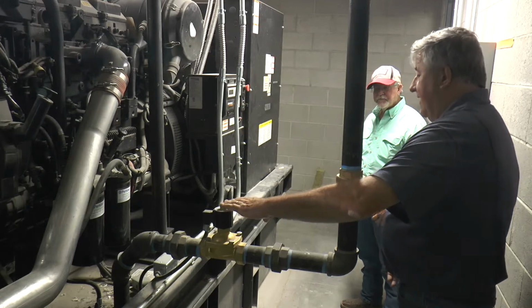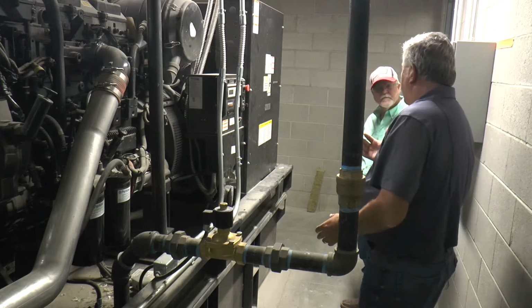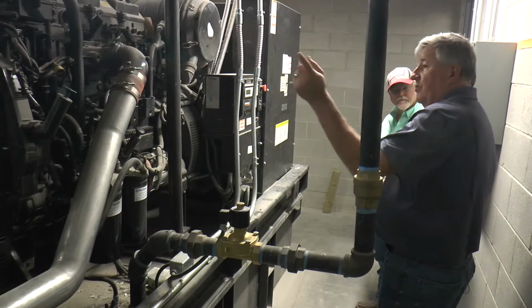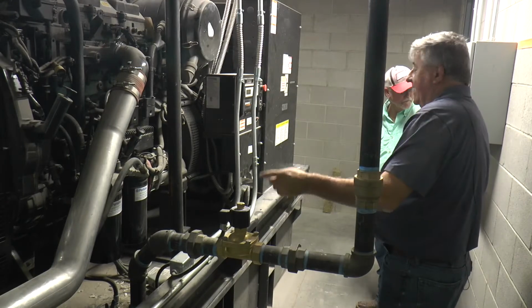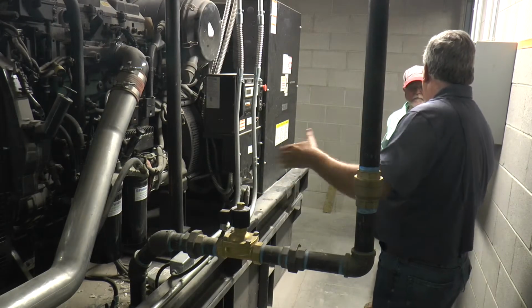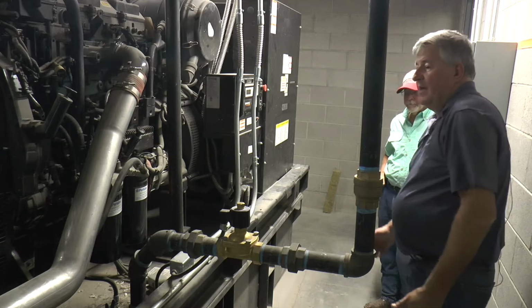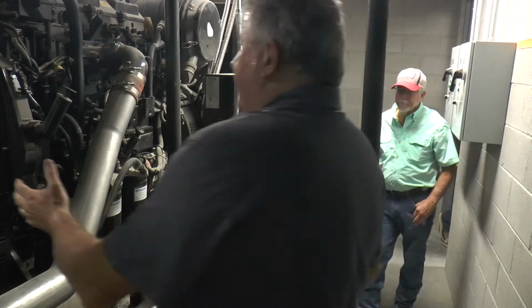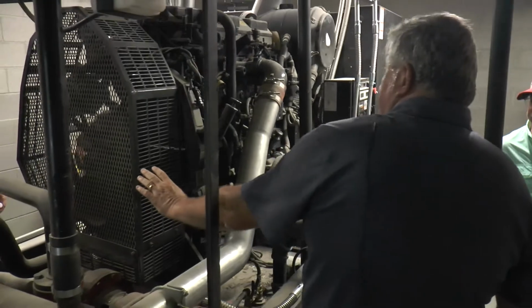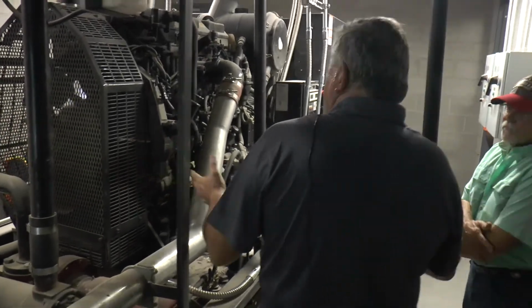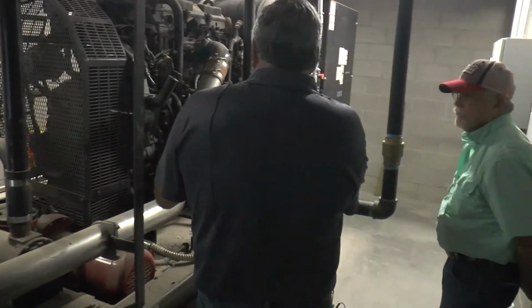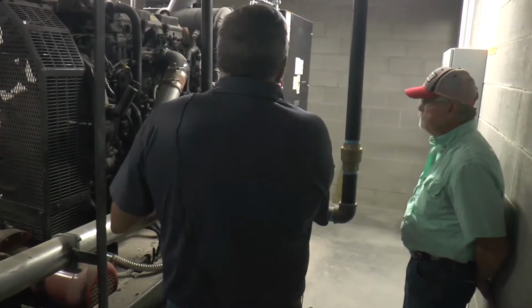So we have a solenoid valve. In the event that the tank gets at 90%, it will give an alarm, and I'll show you that display. At 95, it closes this solenoid valve and prevents you from overfilling the tank. When you're looking at this side of the engine, you just want to look at the fan belts, make sure that they're not frayed. Please note, it can start at any time.